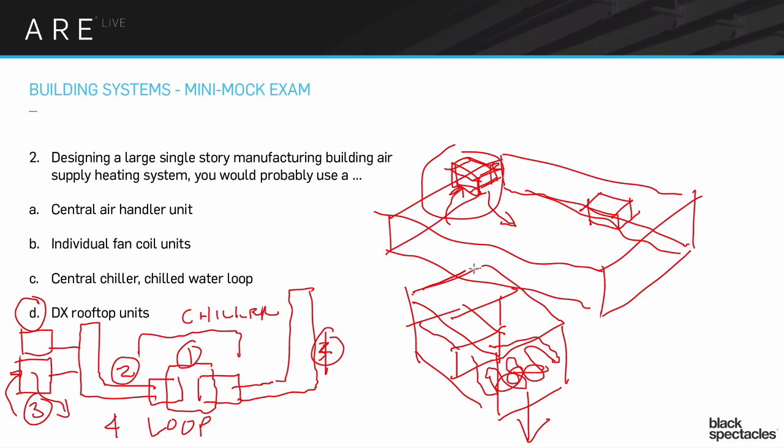And then I have right above that element in the same box, I have this device that has another fan, and it's going to be taking the excess heat that was created and blowing it right out of that big box. So it has its own very tight small heat rejection loop, it has its own refrigerant loop creating the coolness on one side and the hot on the other, and the hot gets rejected out and the cool gets moved over to the coil and we then blow the fan right across it and go straight down into the building.